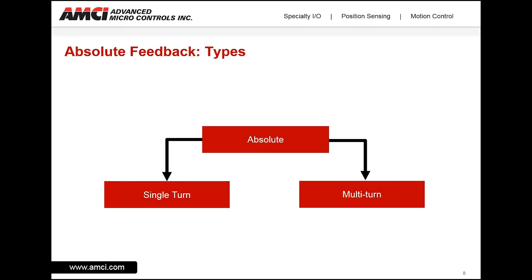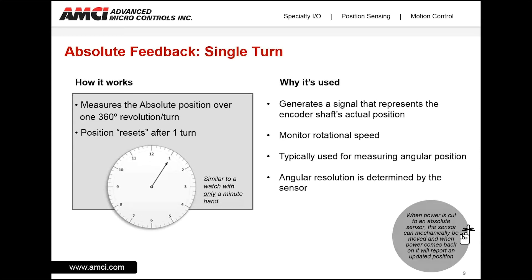Absolute rotary sensors can be either single turn or multi-turn. A single turn application measures the absolute position over 360 degrees or one revolution. After that one revolution, the position resets or starts over — think of it as a watch with only a minute hand; it cannot tell me how many hours have passed. Single turn sensors are used to generate a signal that represents the encoder shaft's actual position, monitor rotational speed, and measure angular position resolution. The angular resolution is determined by the sensor and can provide up to 16 bits of absolute position feedback depending upon the sensor.